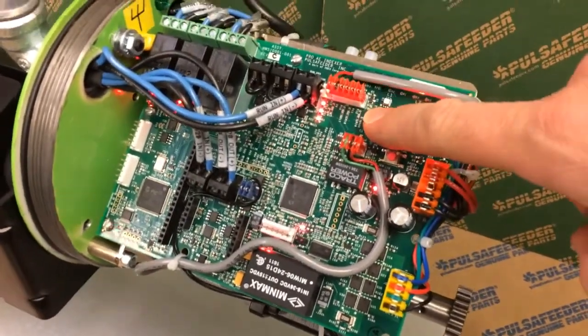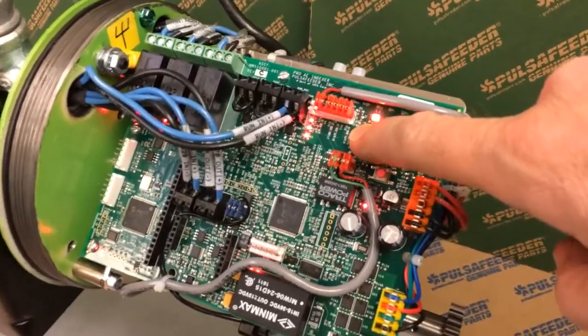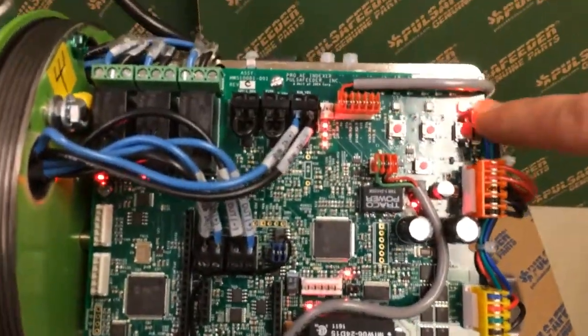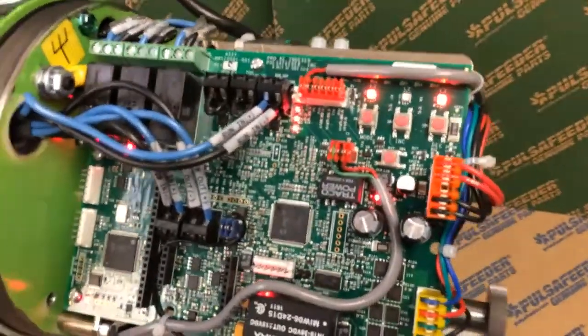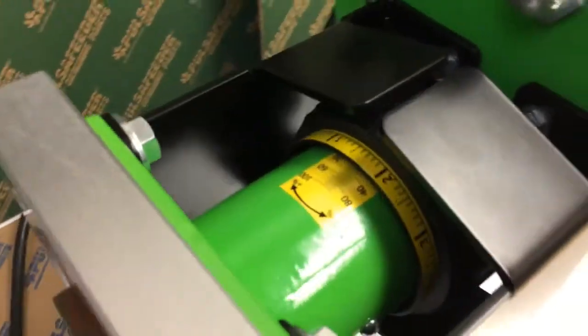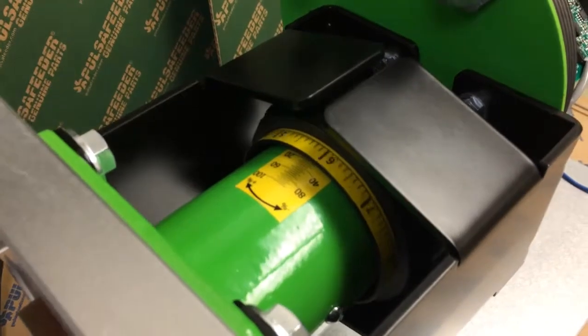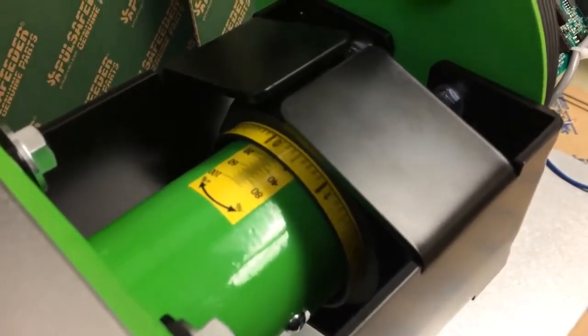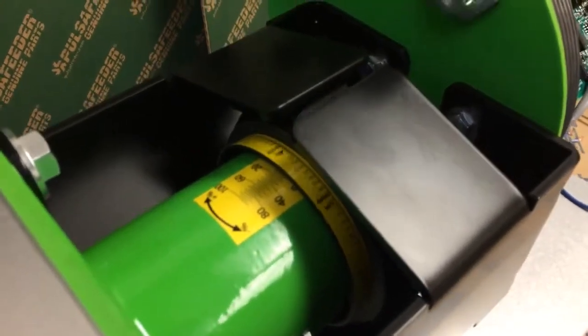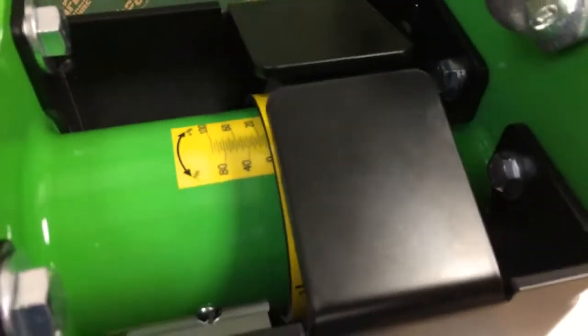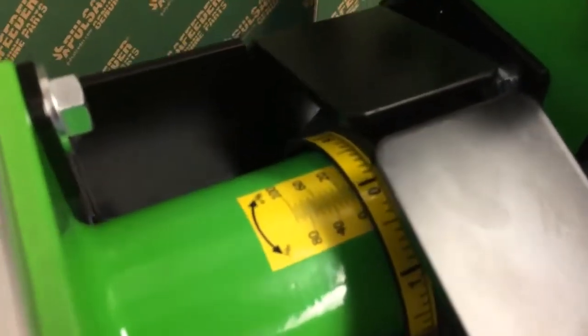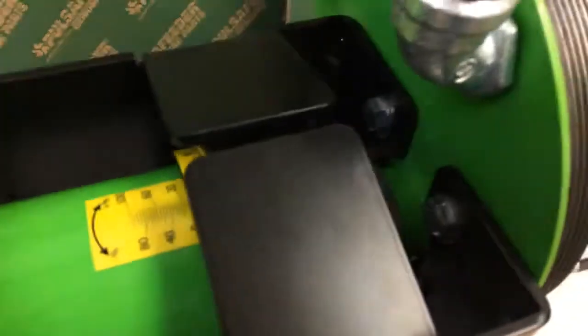I press the little flashing light mode indication, and the first thing it's going to do is reduce the value. That little decrease LED is on, and it's going to start to run the output. You need to be careful because the pump is being adjusted during this process, so you need to take care to make sure that the output of the pump is safe and redirected. Now it's going to take me to an approximate 0 point. Actually, it's about 10% above 0, and it's going to allow me to adjust that to an actual 0% reading. So it's reading almost exactly 10% right now.